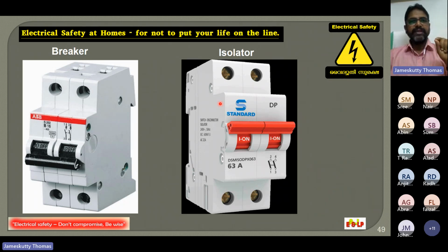In such occasions, we need an isolator placed near the water pump. Here the isolator is only for supply isolation purpose. It will not give protection like a fuse or MCB. It is only for isolation. It's just like our normal switch, our normal house connection switch.